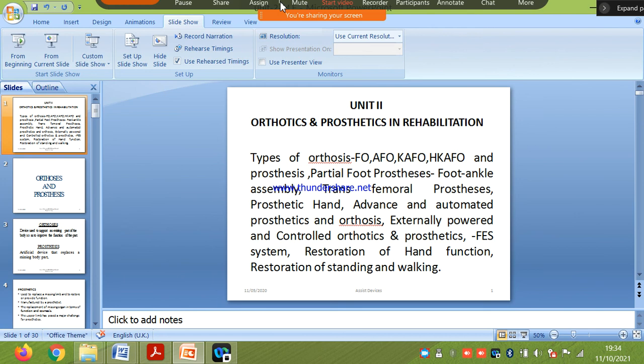We discussed the power systems and materials used in prostheses: metals, plastics, fiber glass, and carbon fiber. We have seen all the components of a prosthetic hand: for body-powered prosthesis — socket, body, harness, suspension system, control system, terminal device, and cosmetic components. For upper limb prosthesis: harness, socket, and cable system. We discussed classification of terminal devices, and the myoelectric prosthesis — where EMG signals are picked up from the upper elbow part, given to the artificial limb, and with battery power the motor rotates under EMG signal control. We discussed the advantages and disadvantages of myoelectric prostheses.